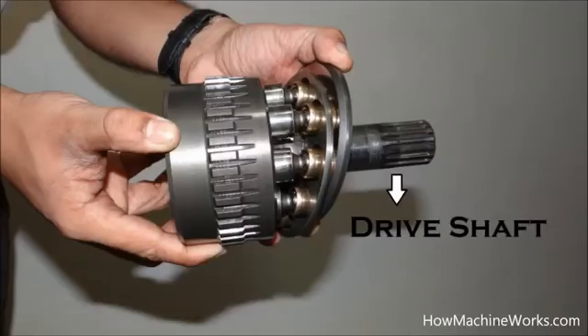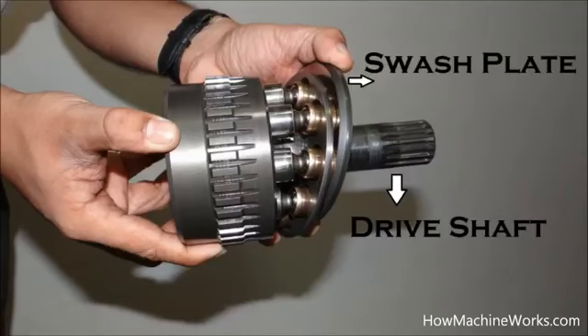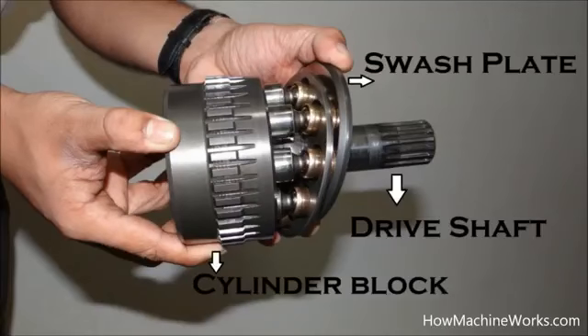Okay, now let's go and have a closer look and identify each component over there. That's the drive shaft, which is a part of the cylinder itself. The drive shaft gives drive to the cylinder, and that's the swash plate, which I told, the pistons are resting and sliding over. The swash plate angle changes, the flow varies. That's our cylinder block in which we have the pistons arranged, and as the cylinder block rotates, the pistons slide over and axially reciprocate. That's the pistons over there.